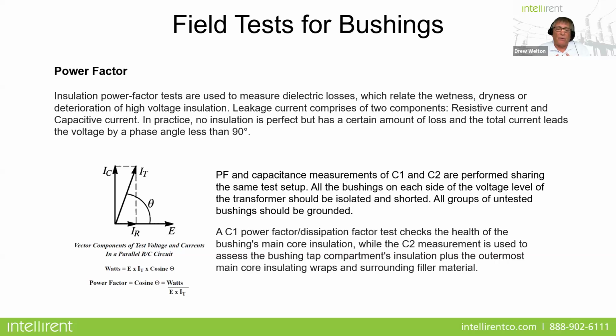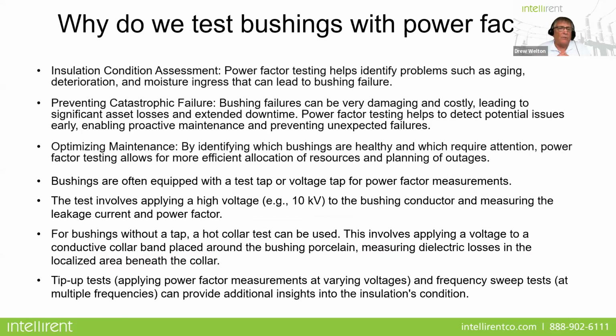A C1 dissipation power factor test checks the health of the bushing's main core insulation, while your C2 test measurement is used to assess the bushing's tap compartment insulation, plus the outer main core insulating wraps around the surrounding filler material. I know that a lot of people may not typically do a C2 test, but I would consider it to be very important. One of the reasons I think it gets overlooked is because a lot of your bushings don't have any C2 nameplate data. So we'll talk about that in just a bit.